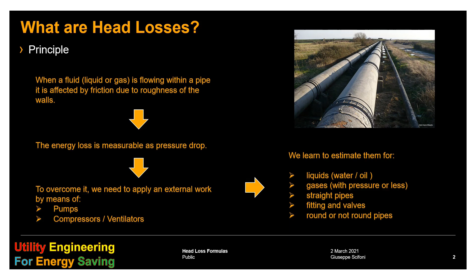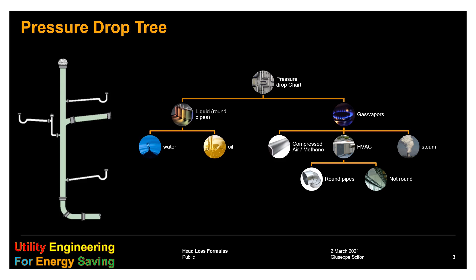We learn in this video to estimate those losses for liquids, both water and oil, for gases with pressure or less, for straight pipes and also for fittings and valves, and for any shape, either round or not round pipes. Here are represented all possible cases, either liquid or gas. Liquids of our interest are water of any temperature and oil. About the gases, we have incondensable ones, like natural gas or air, or even vapors. A special regard must be given to the air ducts for climatization, since they have less pressure and therefore the pipe can be round or even rectangular.